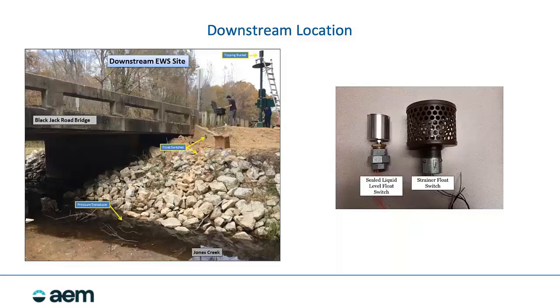What we do like with them, we add some smarts to them. We call them end-of-line resistors. Think of it like a top-notch security system. We have resistors so we can understand the voltage inside the float switch. So if the cable were to get cut, or a mouse chews through the wire, we get that notification that the float switch is damaged and it won't trigger during an event rather than it not being an operational event. So anytime we design a system, we really want to be conscious of this.